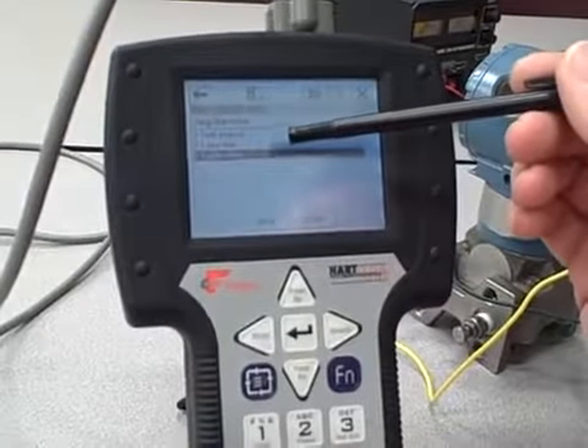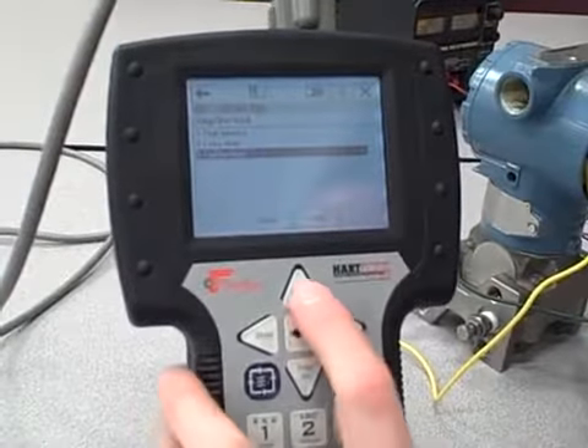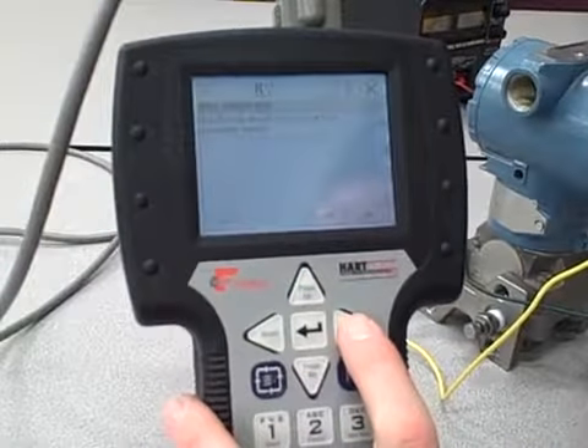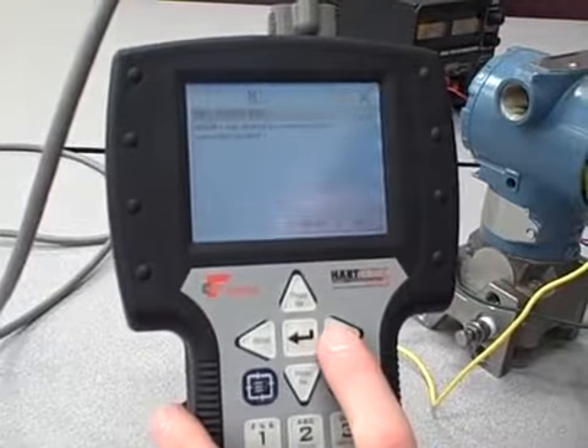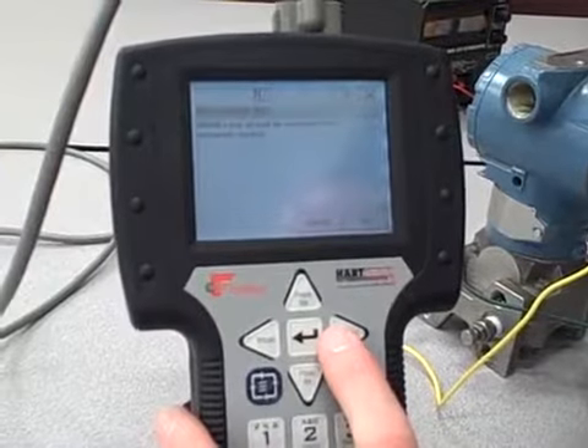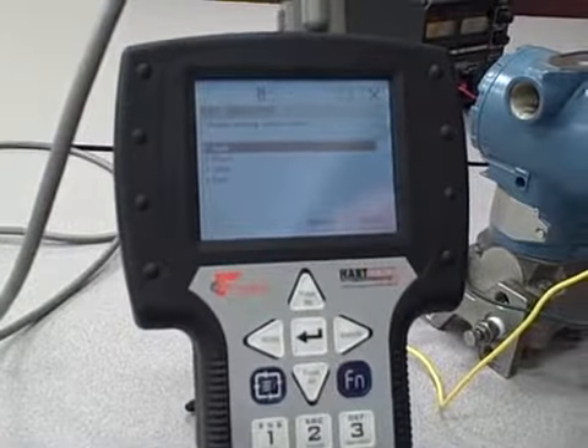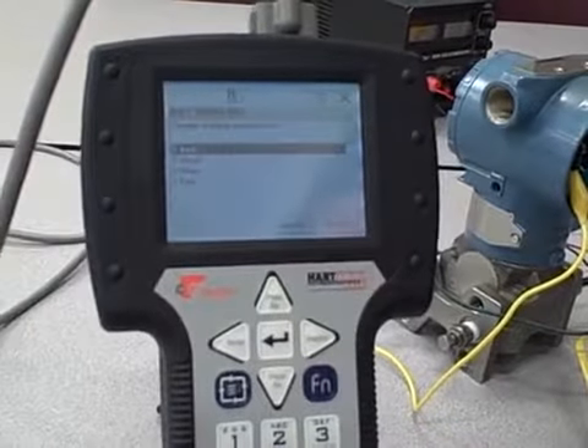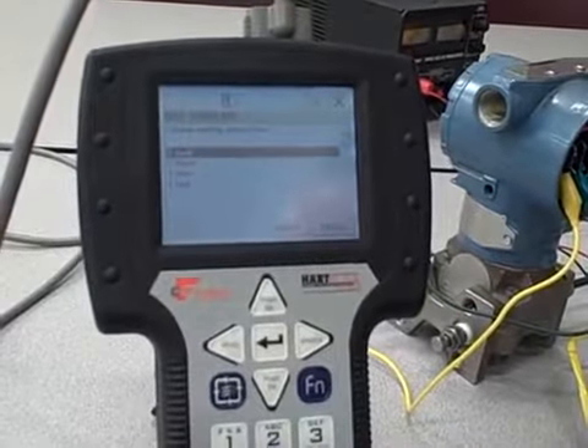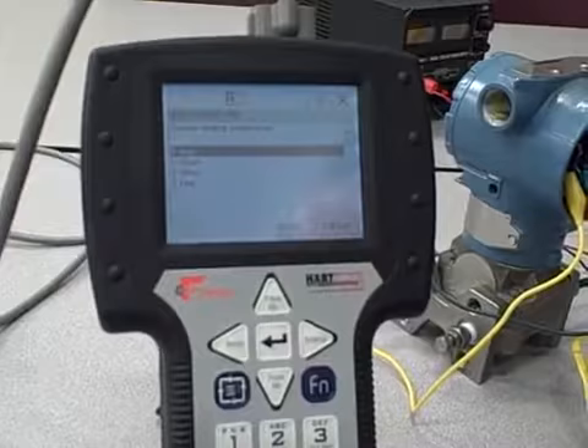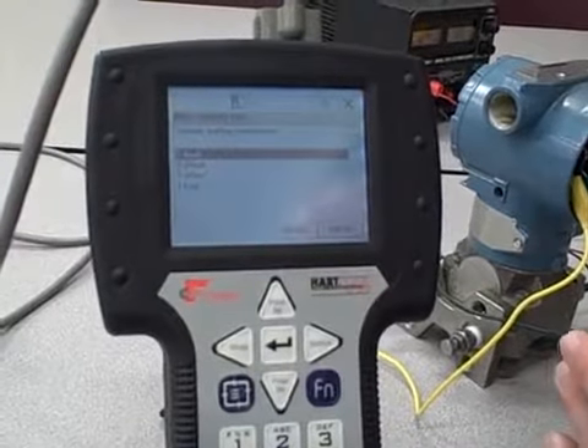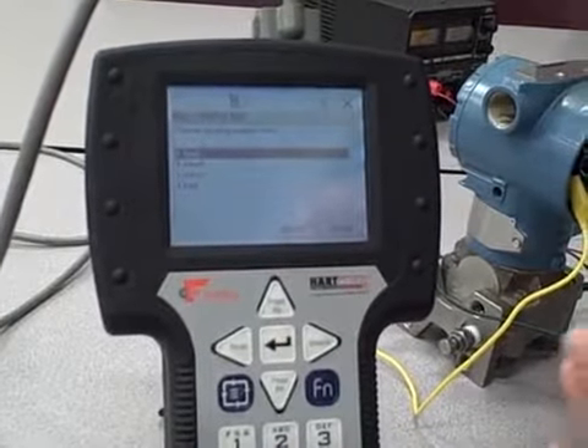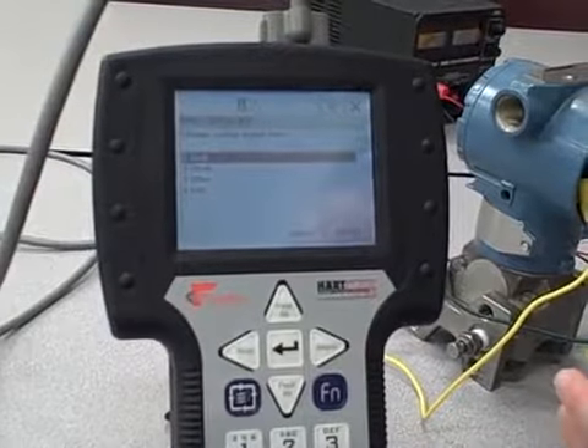The loop test is something that bears some exploration, so I'll step into that. It gives you the obligatory warning: the loop should be removed from automatic control. Choose the analog output level. What the loop test feature allows us to do is force the analog current output signal to whatever value we wish, so it will ignore the applied pressure. This is great for checking out loops that are having problems.